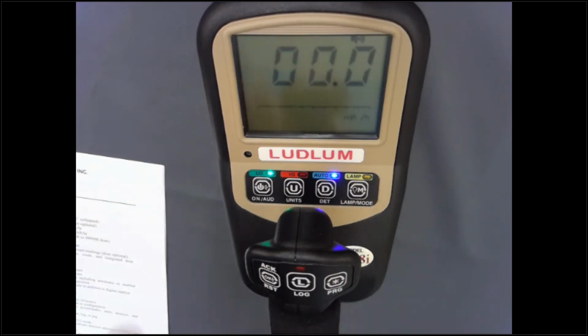If you want to have alarms that transition from your low detector to the high detector, the thing you have to understand is the alarms are based on the current detector. So let's say you want an alarm on your low detector at 5 MR per hour. You can do that and set it up for your low detector. But if you're in auto ranging mode and you switch from the low detector to the high detector, you essentially no longer see the alarms for the low detector, but that's okay because we have 3 alarms on the high detector. So we could also copy over and say that on the second detector or the high detector, we want to have a 5 MR per hour alarm, and then maybe set up a 5 R per hour alarm, and then whatever third alarm that you want. And so when it switches, it will automatically pick up the new alarm and continue to display it.